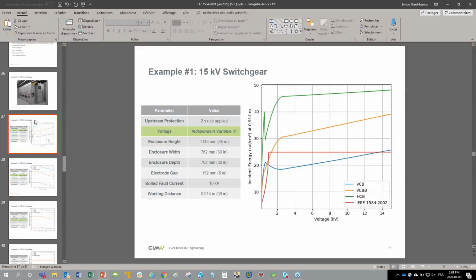Let me ask an additional question. Do any utility companies in your experience provide trip times for a worst case fault that they can support? Well, basically, they give you curves for their fuses and their relay settings, but they don't normally give you a maximum value. But the 2 seconds, it's because the worker has time to go away from the arc flash.